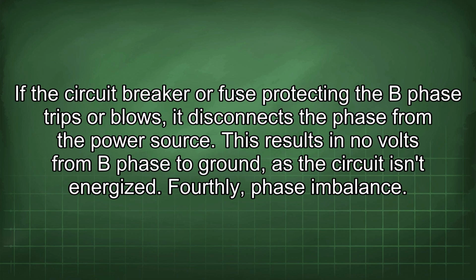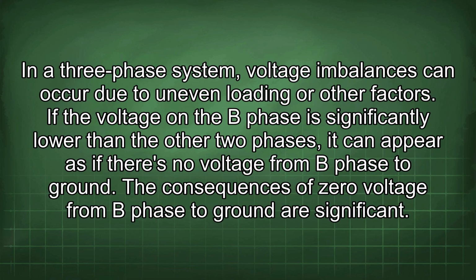Fourthly, phase imbalance. In a three-phase system, voltage imbalances can occur due to uneven loading or other factors. If the voltage on the B phase is significantly lower than the other two phases, it can appear as if there's no voltage from B phase to ground.